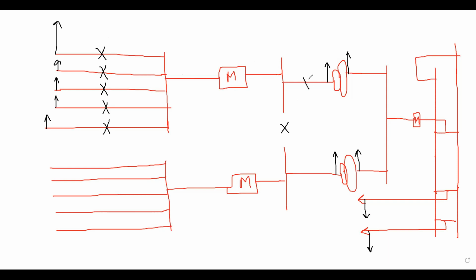And on either side of the transformers, for the protection of the transformer, we require the breaker. And after the transformer, we require the breaker. And in the 220 kV, for this double bus bar protection, everything, we require a breaker. And the bus coupler, we require a breaker. And for the lines, we are having the breaker. We require the breaker. Right, team?